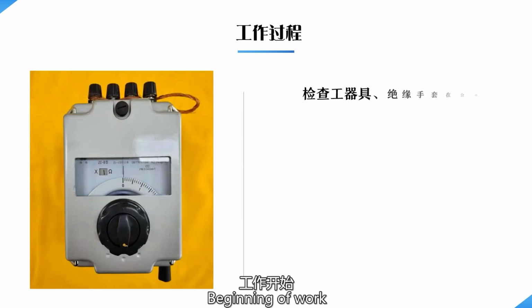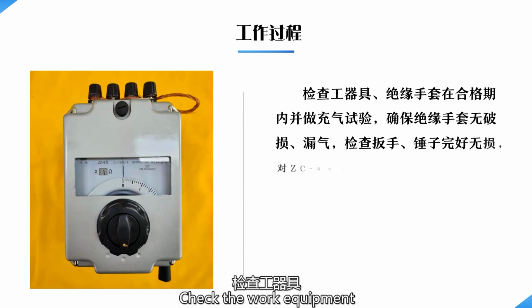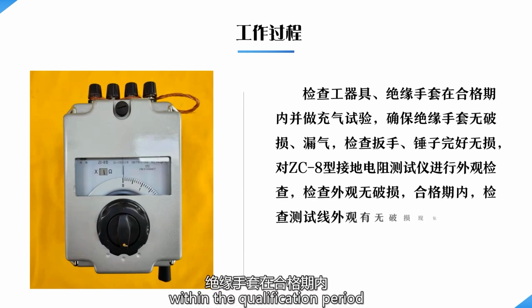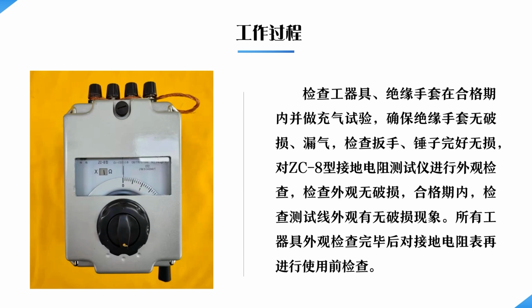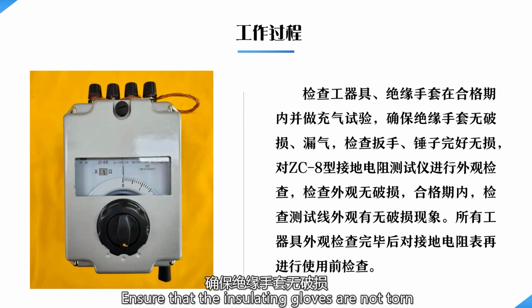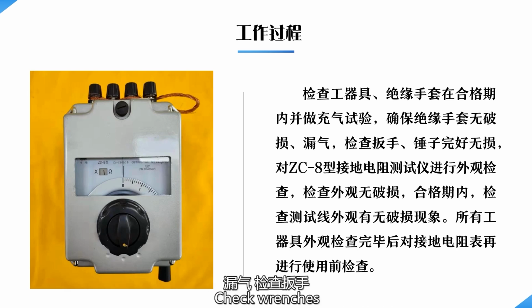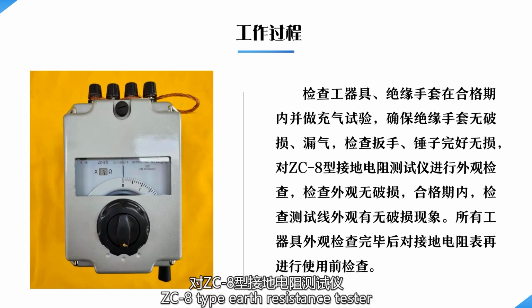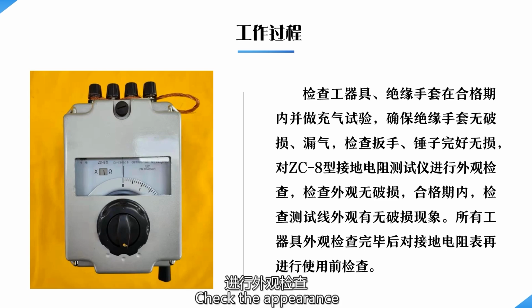Beginning of work: check the work equipment. Insulated gloves must be within the qualification period, and do the inflation test to ensure that the insulating gloves are not torn. Check the wrenches. Check that the hammer is intact. Check the ZC8 type earth resistance tester: check that its appearance is free of damage.